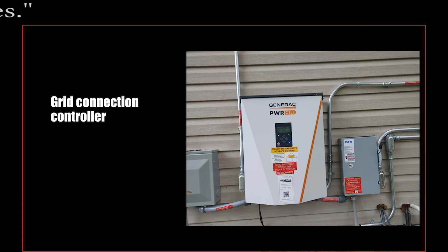That's the reason most backup systems historically installed are dead-throw-over types: they can't come online if you're still connected to the utility. Or if they do come online while connected, they provide no feed until you actually transfer your load to them, so you're showing the utility you're not in parallel with them. In theory, everywhere in the United States you're supposed to have the opportunity to put your system in parallel with the utility and have power flow in either direction at any given moment.